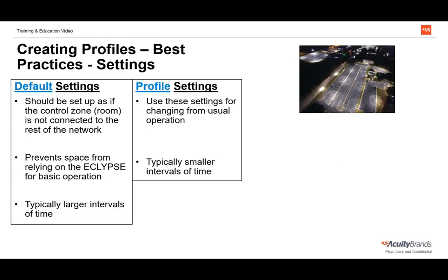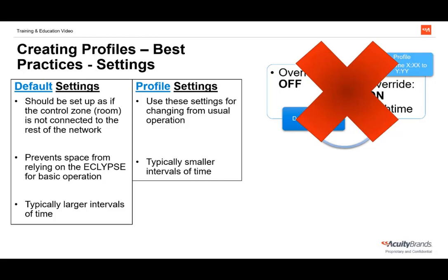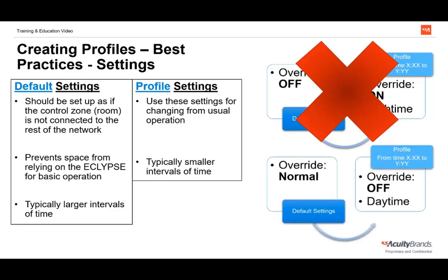Let's use our exterior lighting example. If we used a profile to run at night to override exterior lights on, we'd need the default setting to be override off for daytime — but we don't want to program this way. If the ECLYPSE lost power and the profile doesn't run, the lights would remain overridden off, leaving people in the dark after sunset. Instead, leave the lights' default override setting at normal — which is on — and use a profile to override the lights off during the daytime. This way, if the profile doesn't run, users will never be left in the dark.